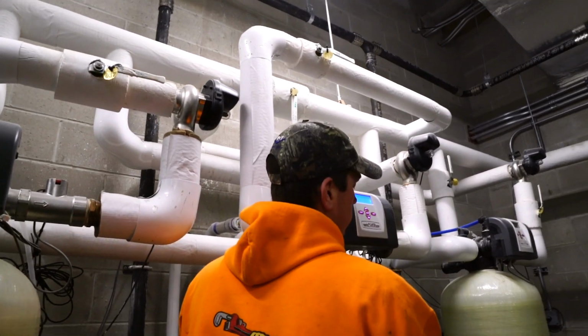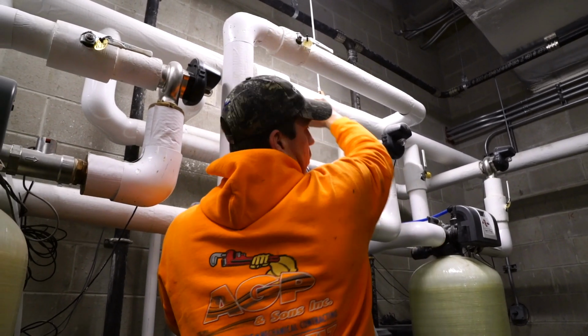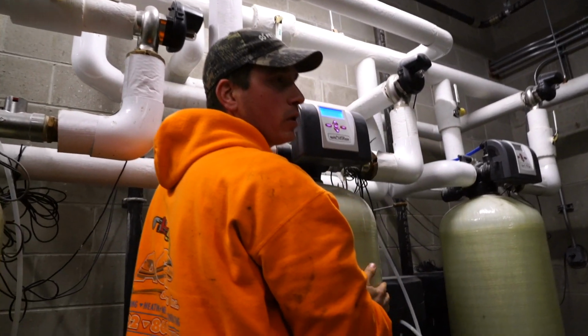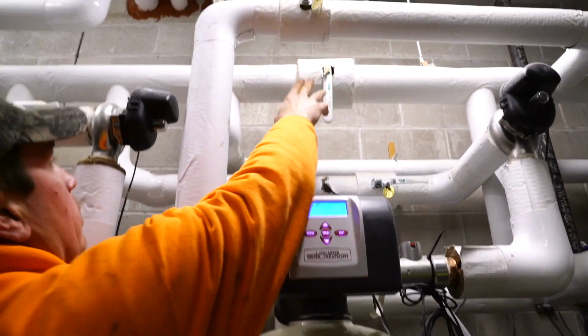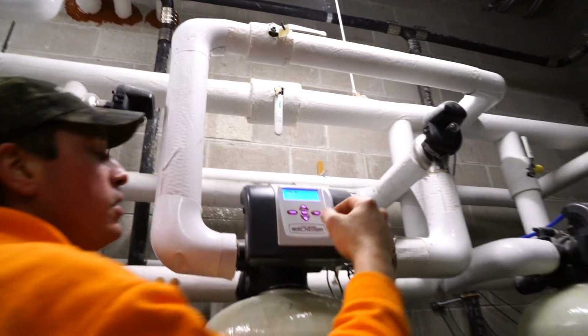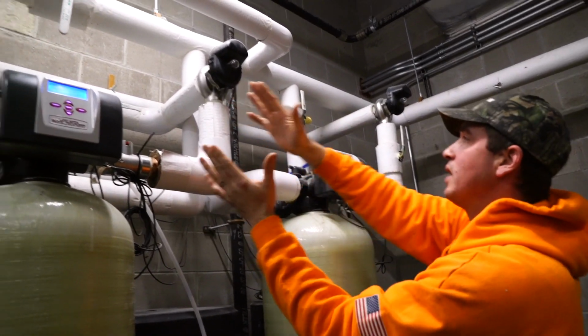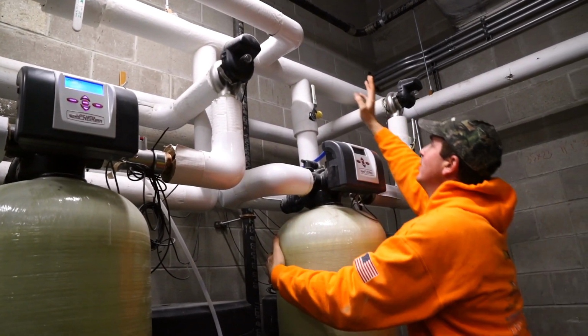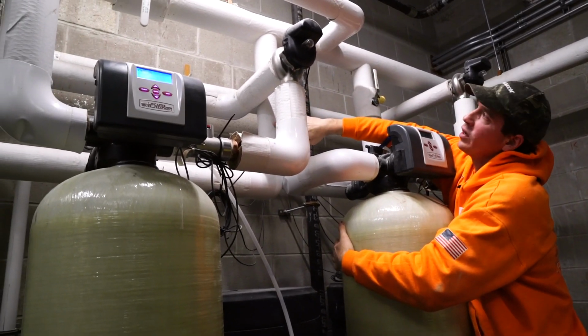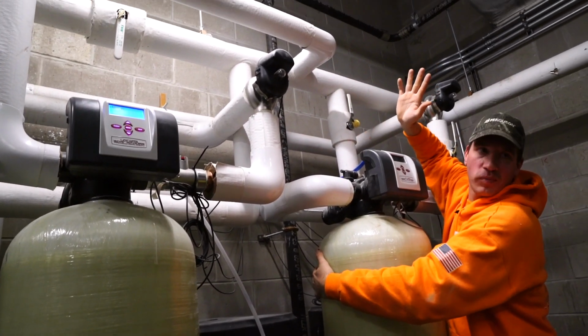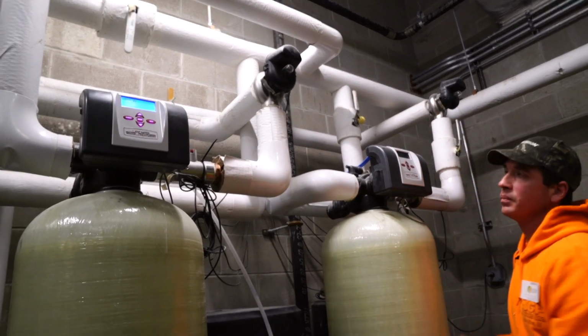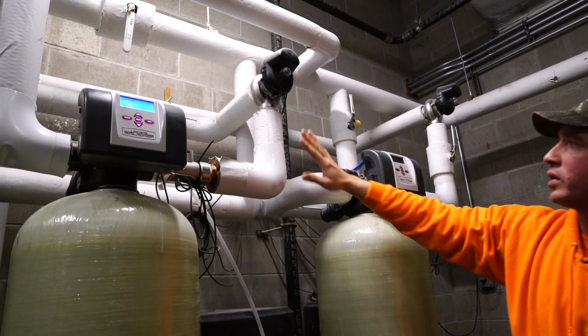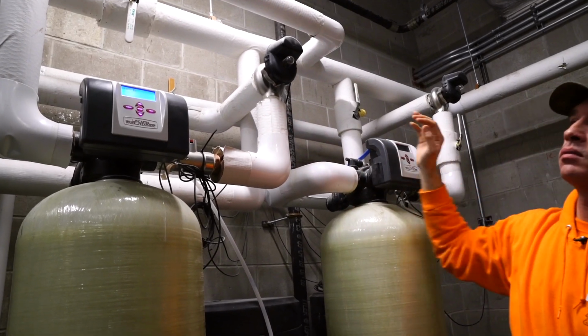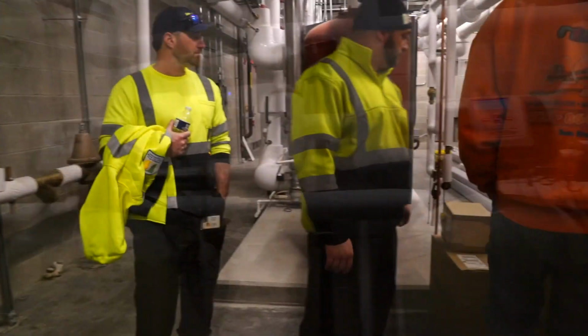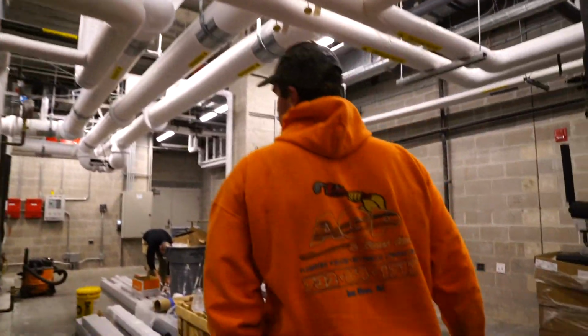So this is a bypass valve. If you ever need to shut these off and not have your filtration system in service, shut all those off, you can still turn that on. You have water to the building. Which one's the bypass? This one right here. Yeah, you can see everything on this side of the bypass valve. You can see 1, 2, 3 all go into the filter. So they're all before the bypass. And then everything on the other side of the bypass valve is all the outside. Out, out, out.